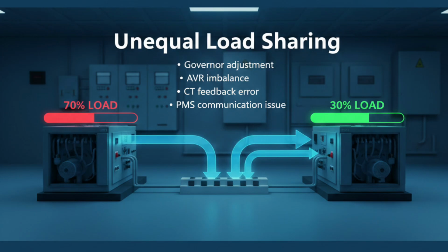Unequal load sharing. On this slide, you see two generators connected to the same busbar but carrying different loads. This is called unequal load sharing. One generator may carry 70%, while the other carries 30%. This is dangerous because the overloaded generator can trip. The main causes are governor setting mismatch, affecting active power sharing, AVR imbalance, affecting reactive power sharing, CT feedback error, or PMS communication problem. Check kW and kVAR meters carefully. Active power depends on governor. Reactive power depends on AVR. Adjust carefully according to manufacturer instructions. Proper load sharing ensures stable operation and prevents reverse power trips.